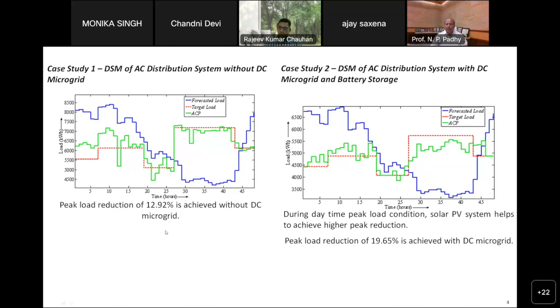Using a battery storage, we added a storage mechanism during off-peak hours to push this curve up, and also discharge during peak hours so this load curve can come down. You can see the green characteristic, which is still better. In the first case, we reduced the peak by 12%. In the second case, the peak was reduced by 19%.